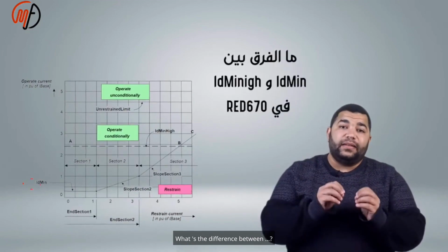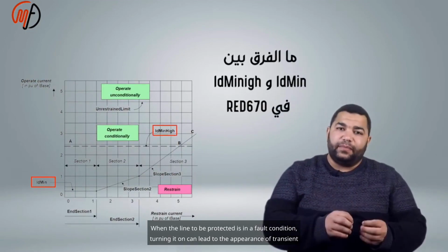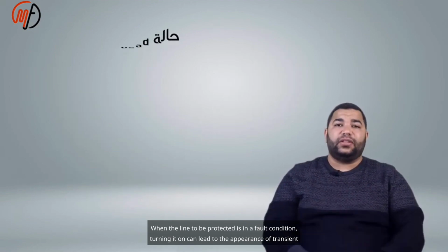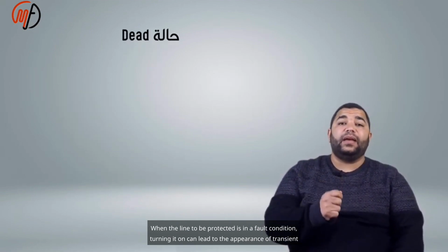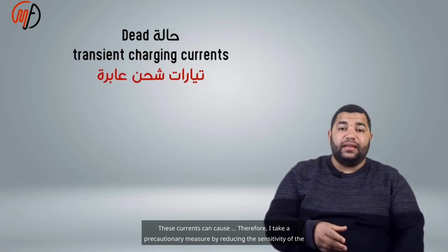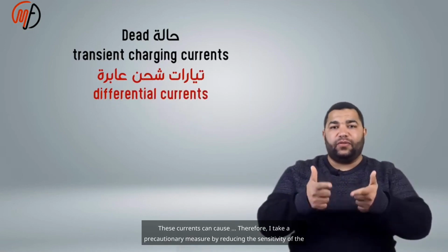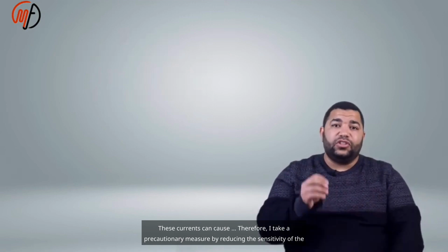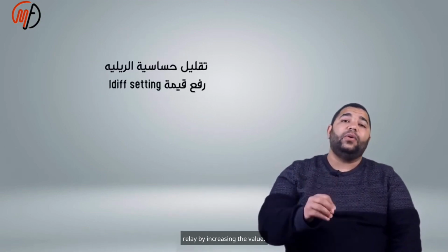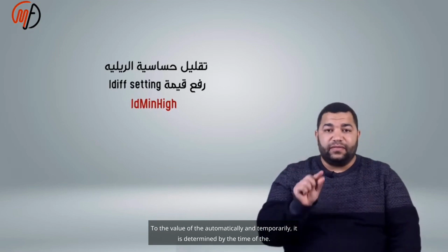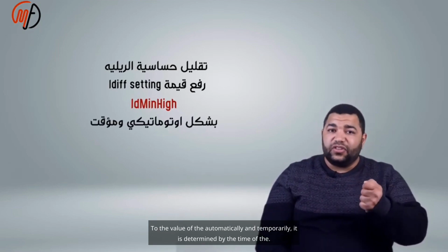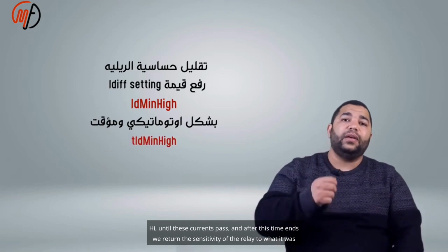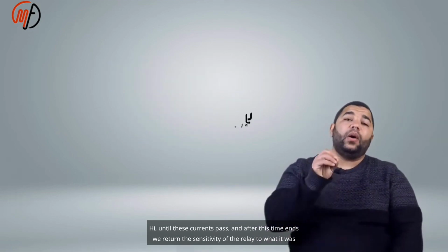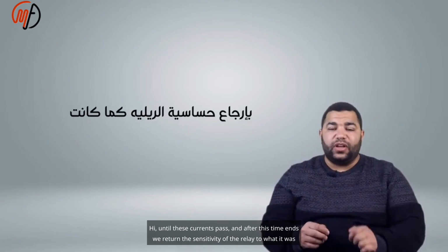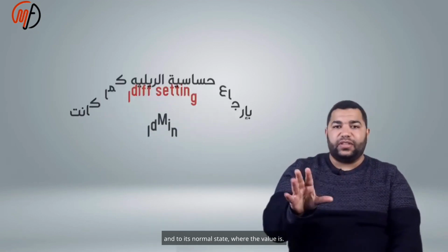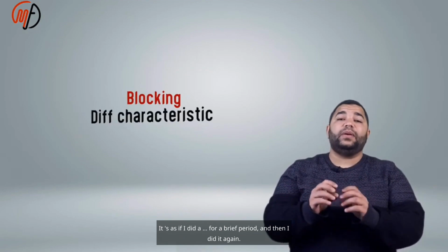What's the difference when the line to be protected is in a fault condition? Turning it on can lead to the appearance of transient charging currents. These currents can cause misoperation. Therefore, I take a precautionary measure by reducing the sensitivity of the relay by increasing the value to the value of the IdMinHigh setting, automatically and temporarily. It is determined by the time of the high setting until these currents pass, and after this time ends, we return the sensitivity of the relay to what it was, to its normal state. It's as if I desensitized it for a brief period, and then I restored it again.